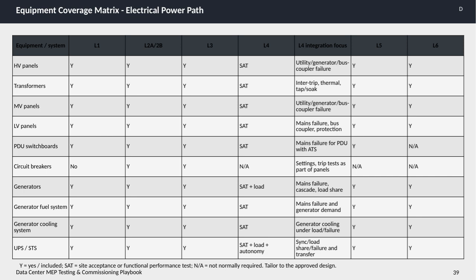Generator systems not only get SATs but also load testing and evaluation of cascade failures or load sharing. At higher levels, L5 and L6, the focus is on more detailed and comprehensive testing, such as synchronization, load sharing, failure response, and transfer mechanisms, ensuring resilience and reliability under operational stresses. The legend clarifies that Y means the equipment is included for that level. SAT refers to site acceptance tests, and not applicable indicates that testing is not normally required for that level. Of course, these are tailored to the approved design of the data center. Overall, this matrix provides a structure and detailed framework to ensure thorough testing coverage across all critical electrical power path equipment, supporting safe and reliable data center operations.